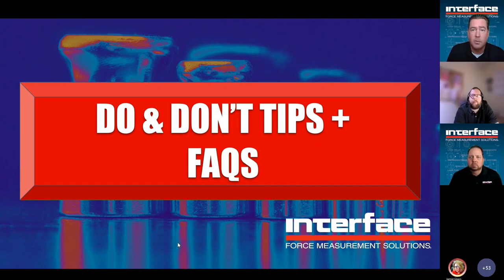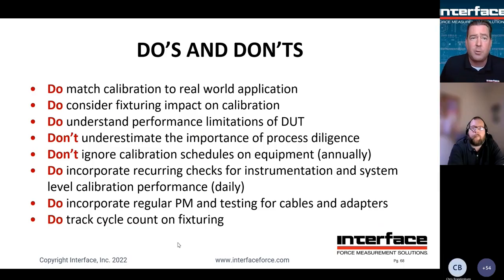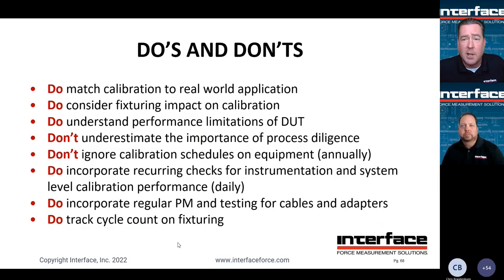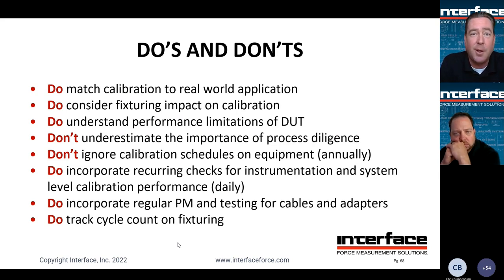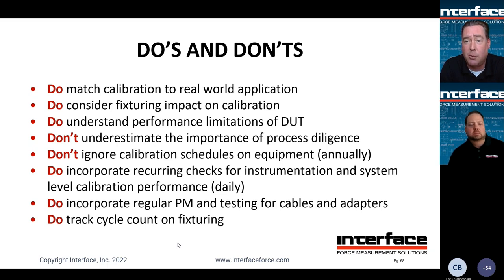All right, thank you, Chris. So we'll try to touch on a couple of do's and don'ts and then touch on some frequently asked questions. This is a compilation of some points we made earlier in the presentation. So do try to match the calibration to the real world application. That's important. Trying to replicate as closely as possible the use case in the calibration frame will yield the best and most real world results for the lowest uncertainty in the actual measurement in the field.